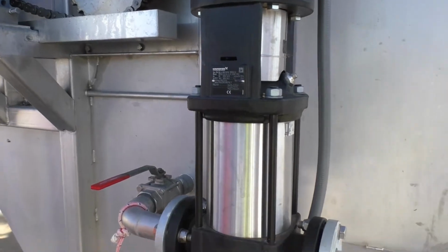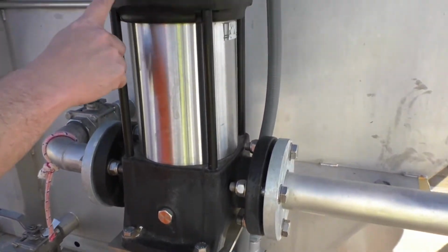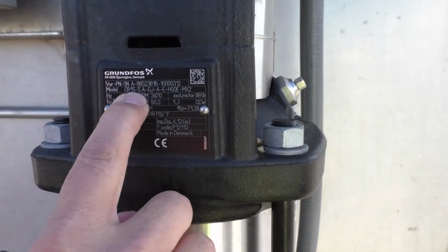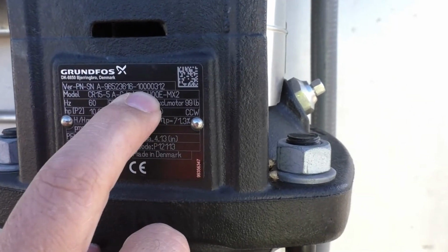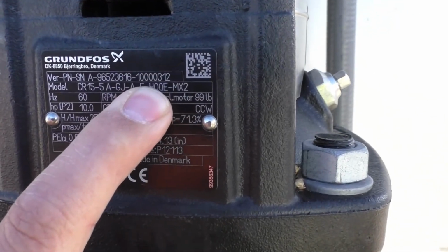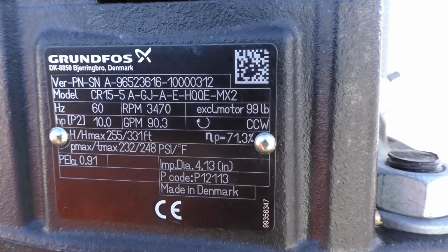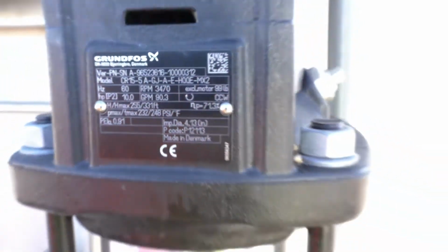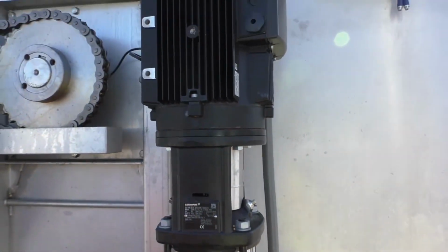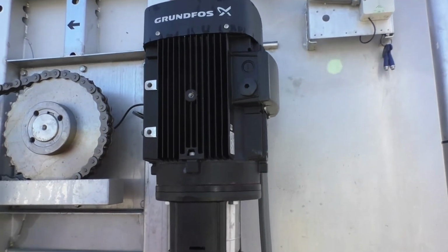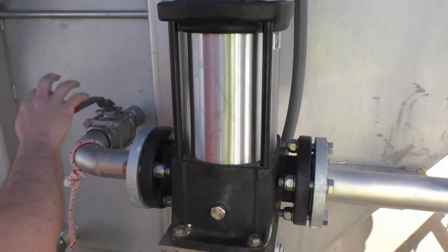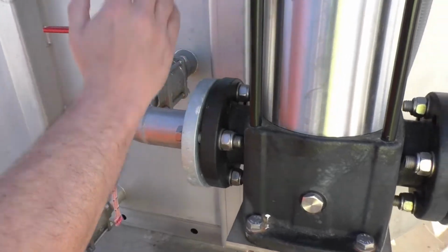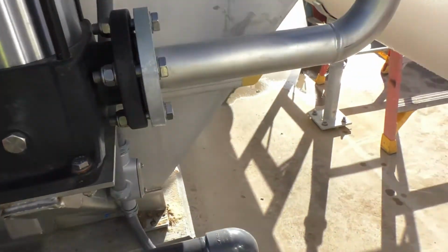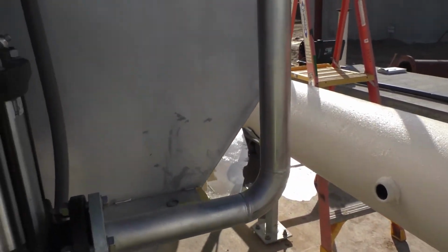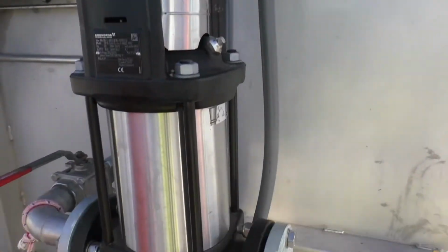On your backwash pump, here's your model. It's a CR15-5. Up here, this is your serial number, which is the 10,312. If you have to take this apart for whatever reason and fill this back up, you have a valve right here. You close the valve. That basically isolates it if you have water on this side, to keep from flooding yourself out. When you install a new one, make sure your arrow right here is going with the direction of flow.